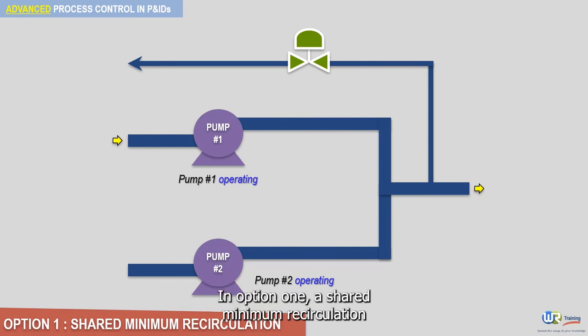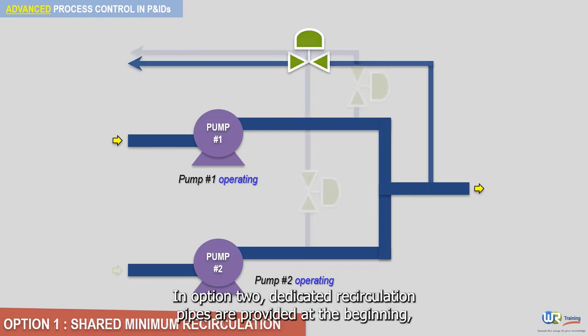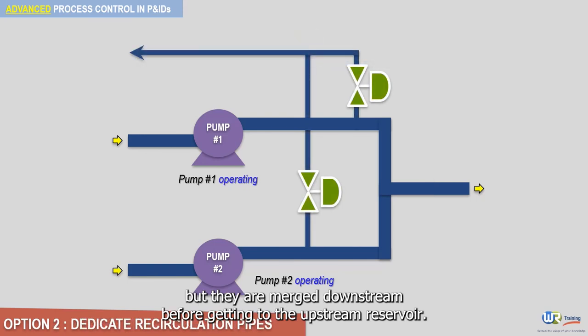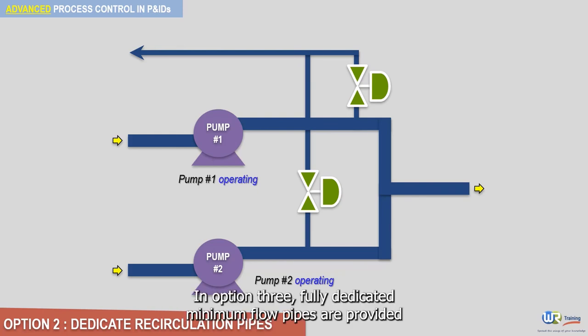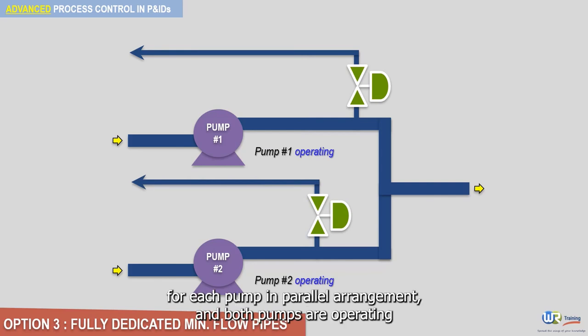We have three options for providing minimum flow lines for parallel operating pumps. In option 1, a shared minimum recirculation pipe is provided for two operating pumps. In option 2, dedicated recirculation pipes are provided at the beginning, but they are merged downstream before getting to the upstream reservoir. In option 3, fully dedicated minimum flow pipes are provided for each pump in the parallel arrangement, and both pumps are operating.